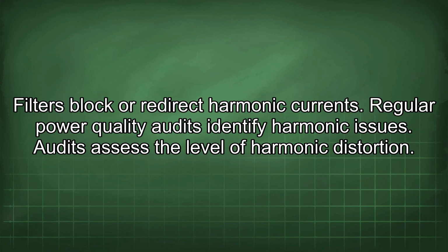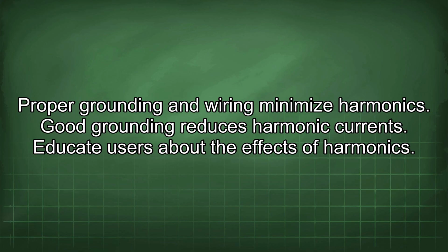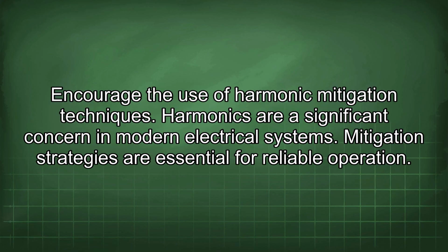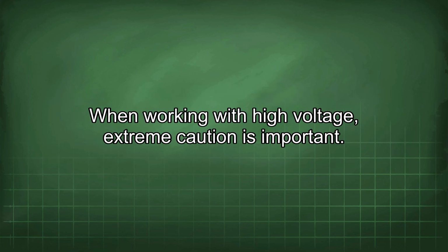Regular power quality audits identify harmonic issues. Audits assess the level of harmonic distortion. Proper grounding and wiring minimize harmonics. Good grounding reduces harmonic currents. Educate users about the effects of harmonics. Encourage the use of harmonic mitigation techniques. Harmonics are a significant concern in modern electrical systems. Mitigation strategies are essential for reliable operation. When working with high voltage, extreme caution is important.